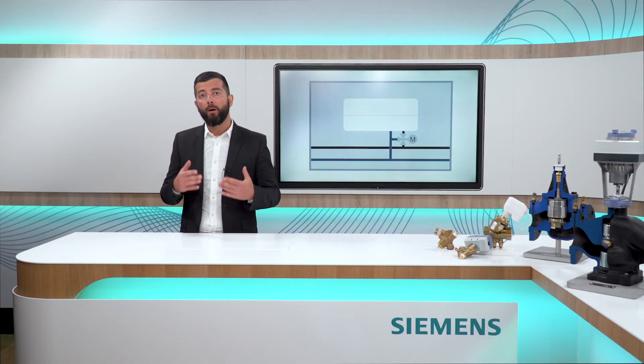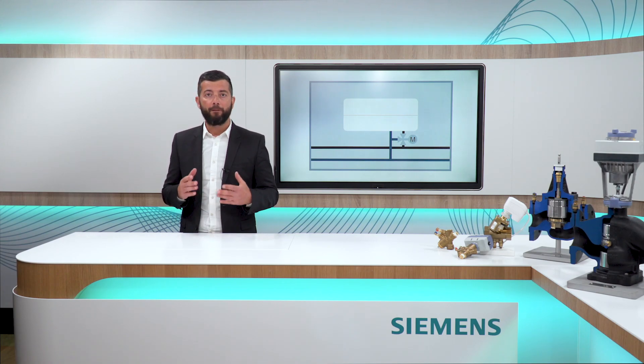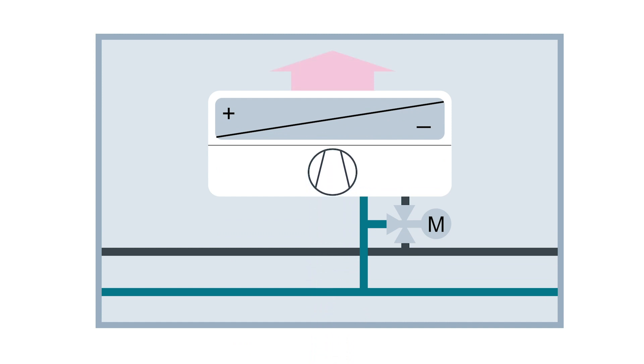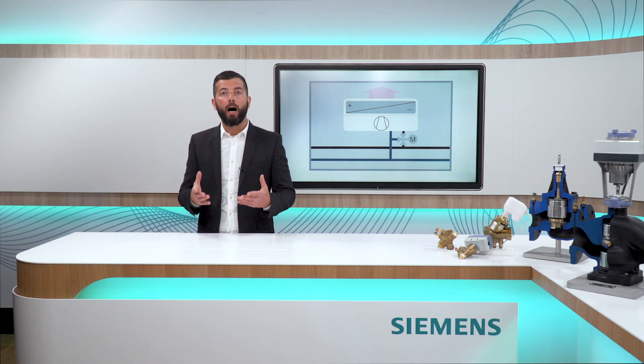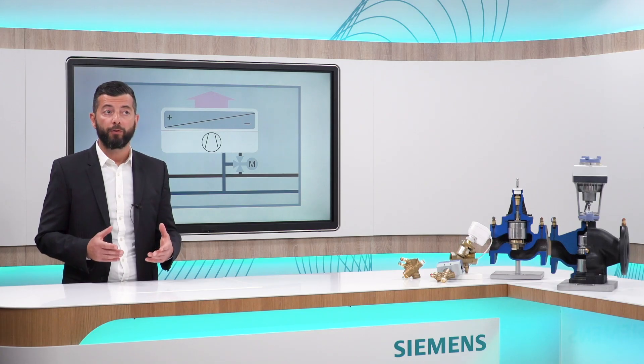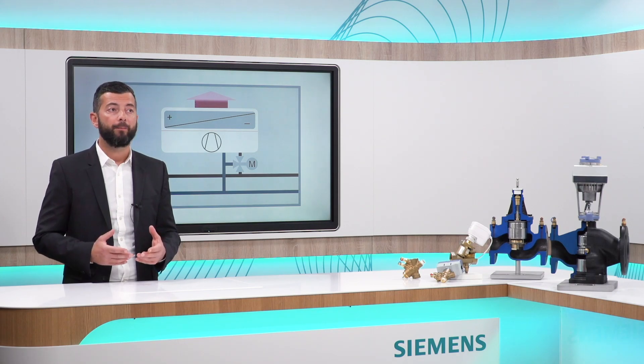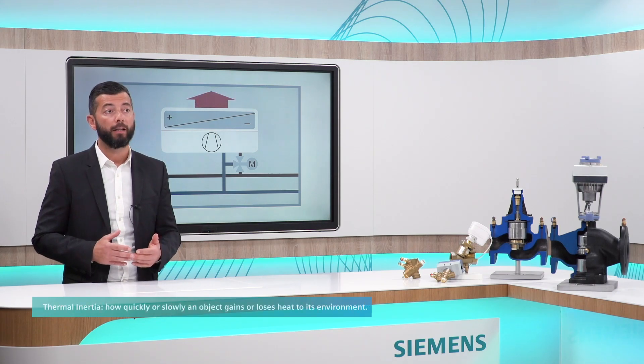Let's start with what is a Fan Coil Unit? A Fan Coil Unit basically consists of a heat exchanger and a fan. It transports the heating or cooling energy from the hydraulic network with temperature-controlled air into the room. Fan Coils are particularly well suited for room applications. If someone changes the room temperature setting, the Fan Coil reacts very quickly thanks to a relatively low thermal inertia.